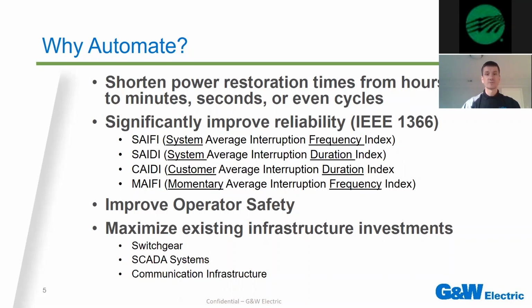Third point I'm making here is improved operator safety. With automation, you increase operator safety by not putting a lineman in front of a live device, or worse, a faulty device, or one that might be submerged in a vault after a storm, or where the operator has to maneuver in tight spaces to hook stick operate equipment. With automation, you can eliminate that by automatically switching devices or moving to a push button operation on a relay or electronic device that's on the 120 AC side rather than 4 kV and up.